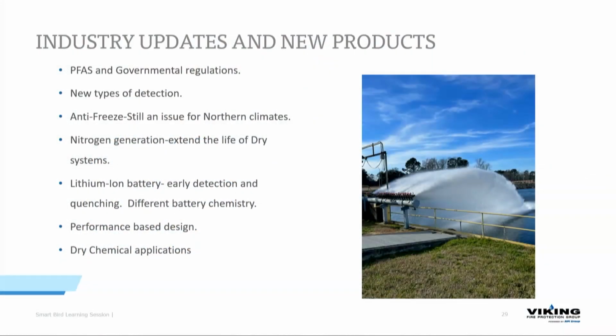You end up having to put a detection system in case there's too much nitrogen? It does. So he asked if you have to put a detection system on there, and it has level monitors. Correct. It's basically an air compressor that has a nitrogen generation component, so it just continually feeds that system. And you'll get a low pressure alarm just like you would regularly if something's escaping.